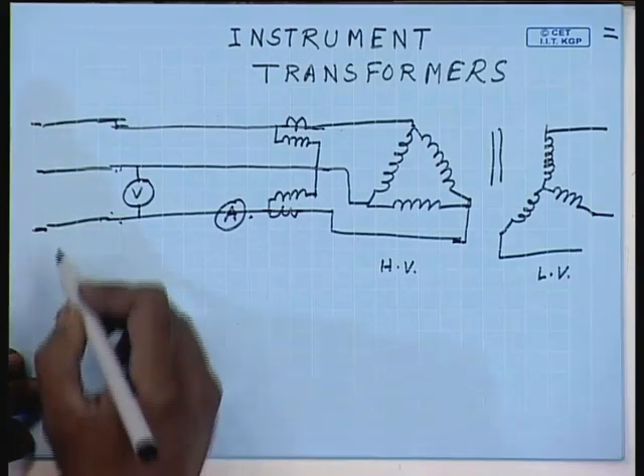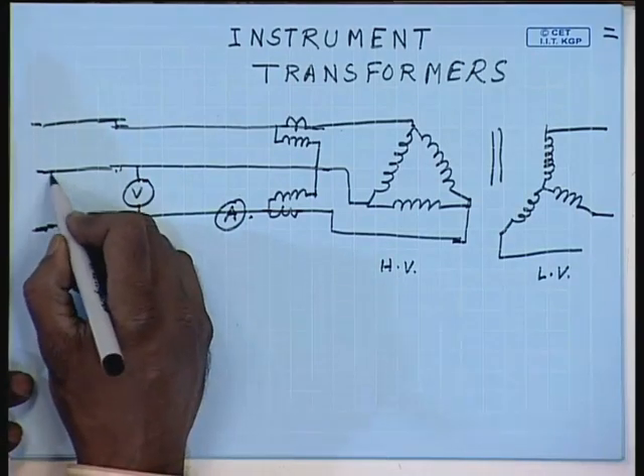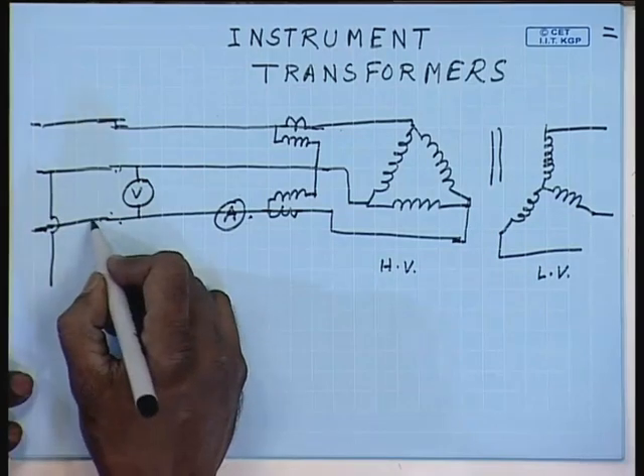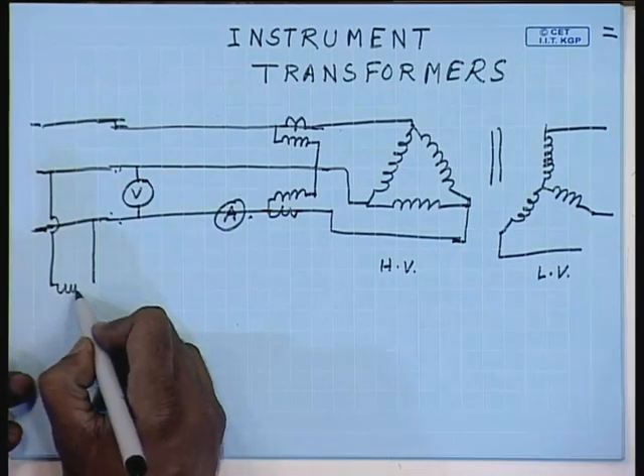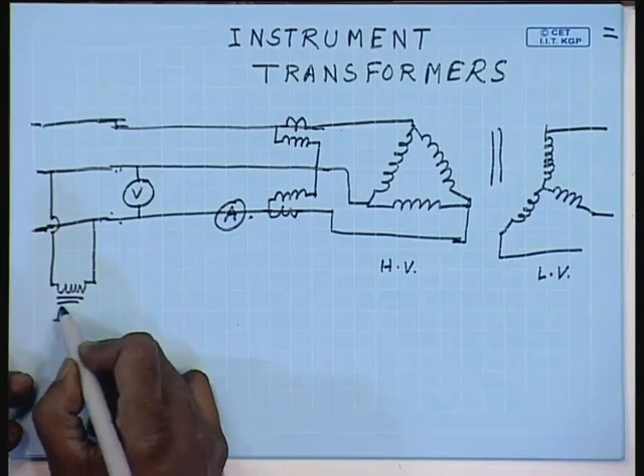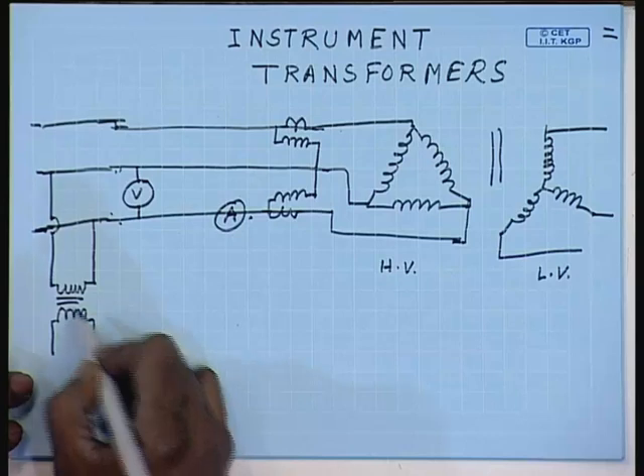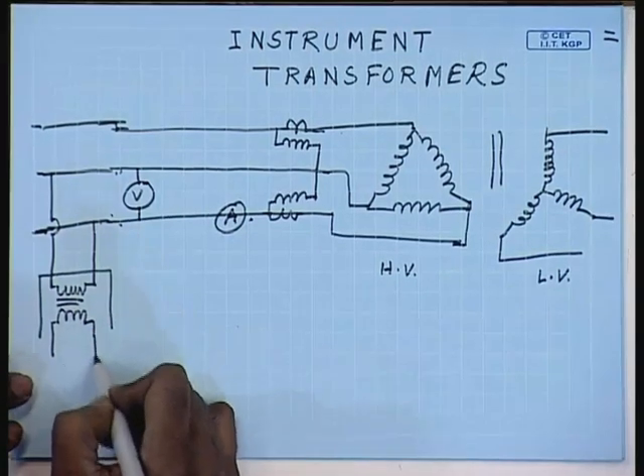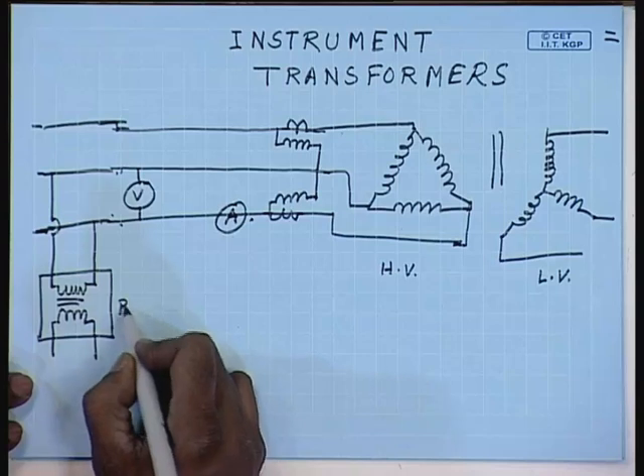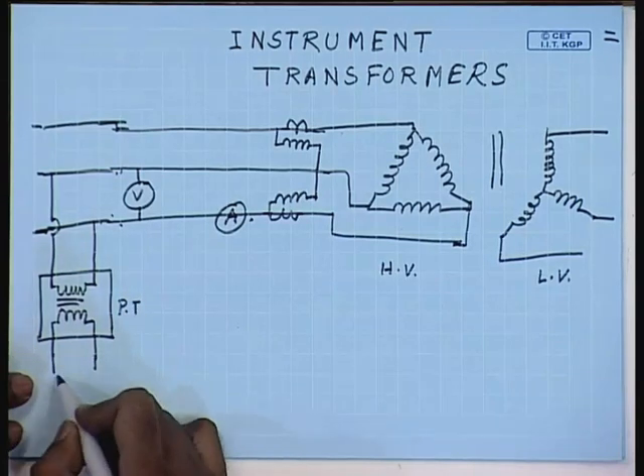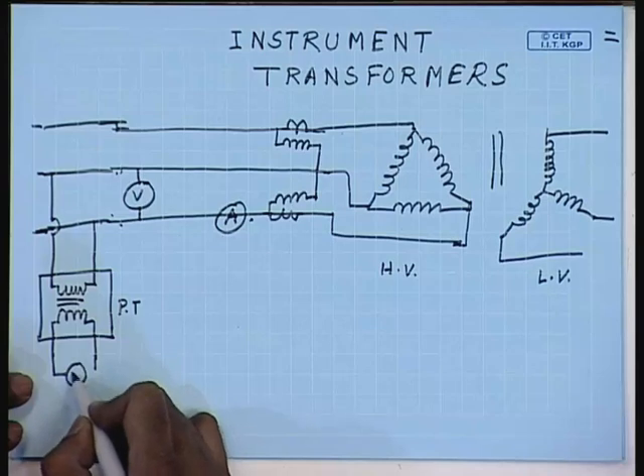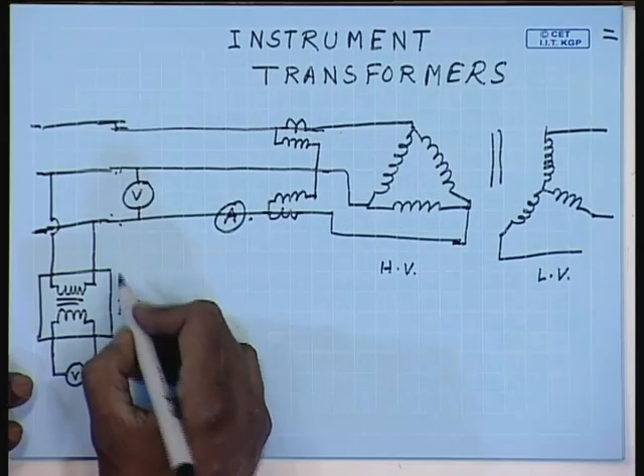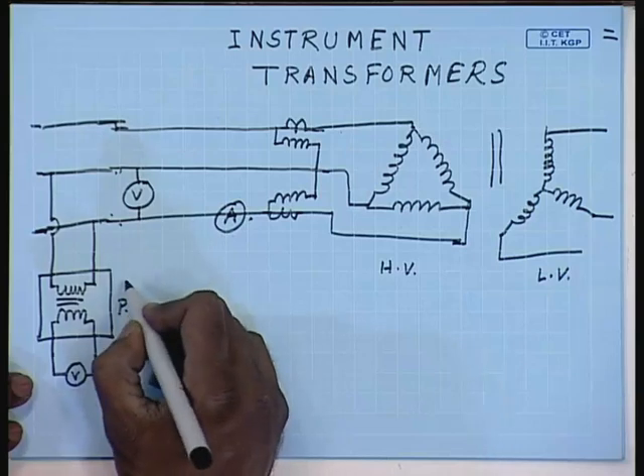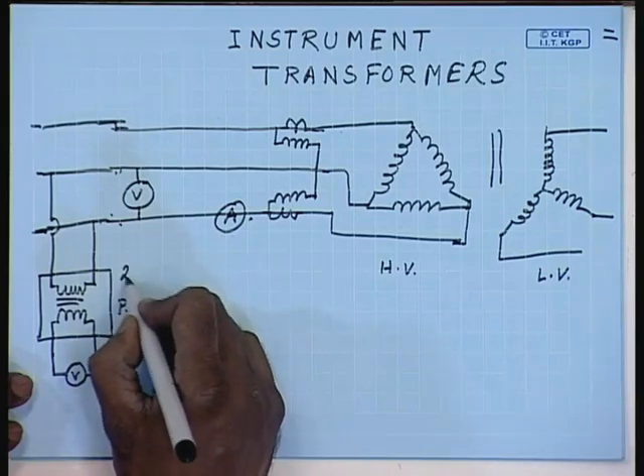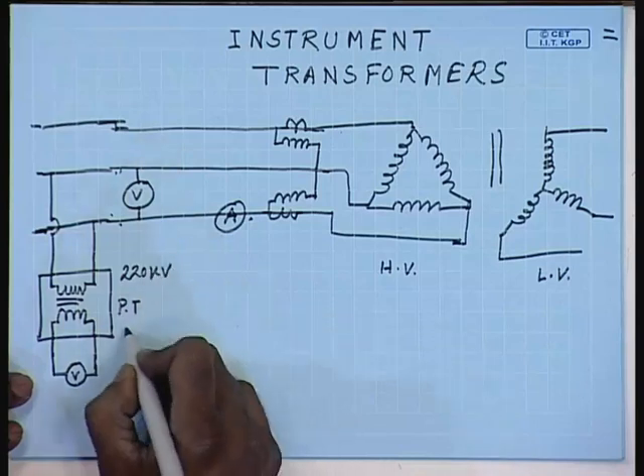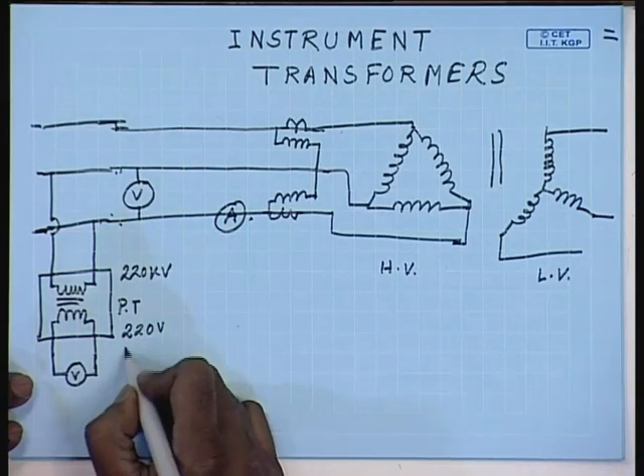Instrument transformers, there are two types. One is used to reduce the voltage level and hence called the potential transformer or the PT. This is the PT, to the secondary of which we can connect the voltmeter. It steps down the voltage, let us say, from some 200 kilovolt to maybe 220 volts, or more often than not 110 volts.